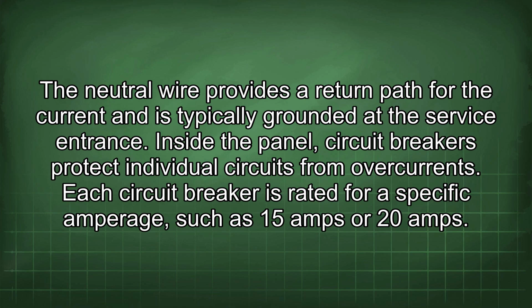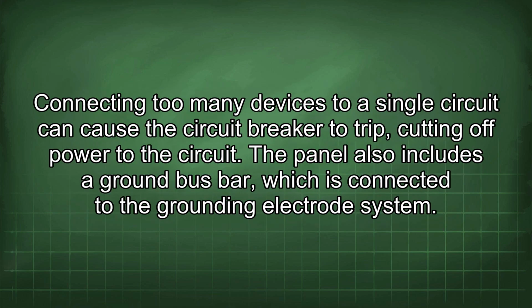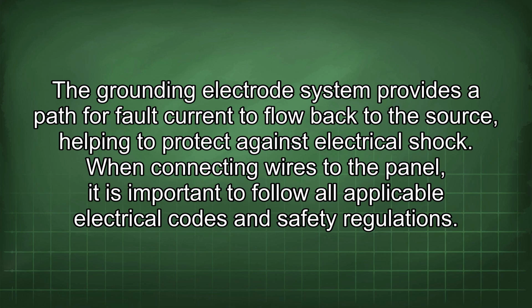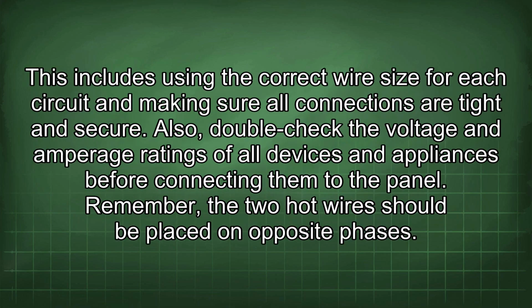Inside the panel, circuit breakers protect individual circuits from overcurrents. Each circuit breaker is rated for a specific amperage, such as 15 amps or 20 amps. Connecting too many devices to a single circuit can cause the circuit breaker to trip, cutting off power to the circuit. The panel also includes a ground bus bar, which is connected to the grounding electrode system. The grounding electrode system provides a path for fault current to flow back to the source, helping to protect against electrical shock. When connecting wires to the panel, it is important to follow all applicable electrical codes and safety regulations. This includes using the correct wire size for each circuit and making sure all connections are tight and secure. Also, double-check the voltage and amperage ratings of all devices and appliances before connecting them to the panel.